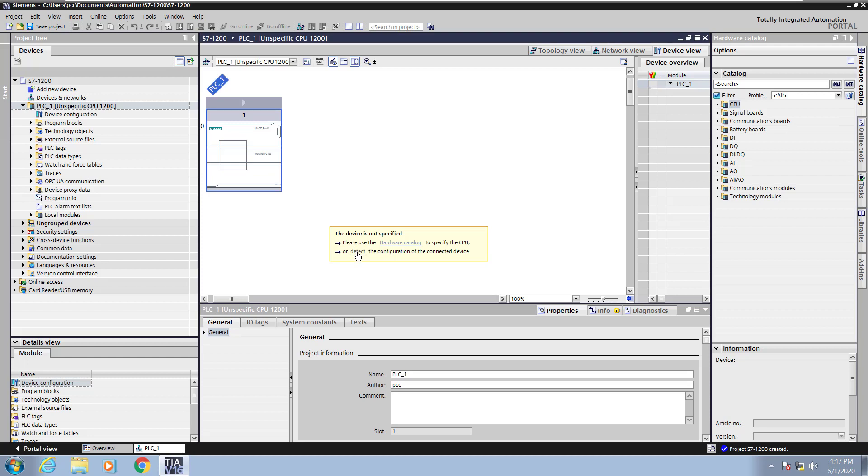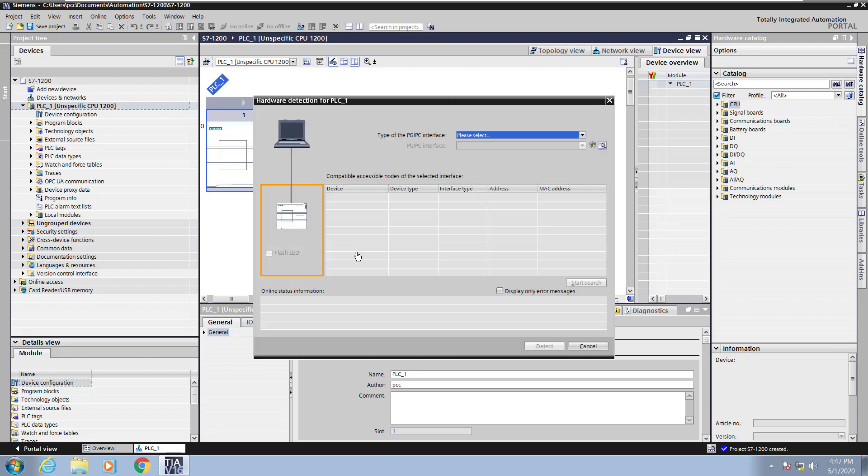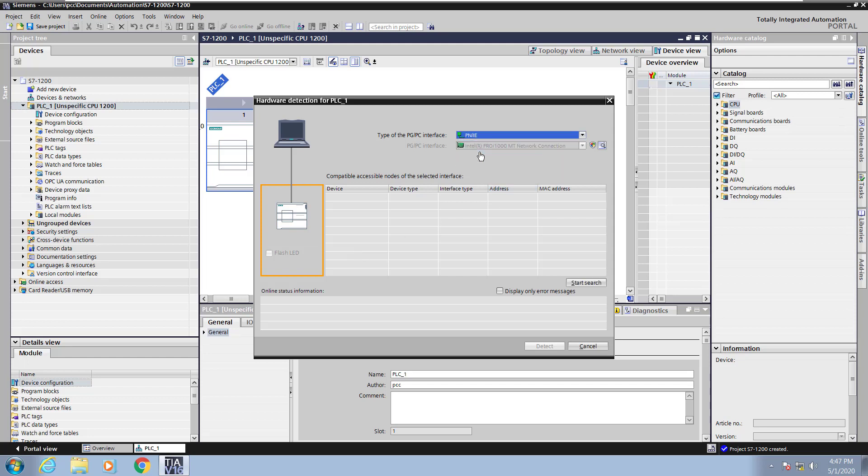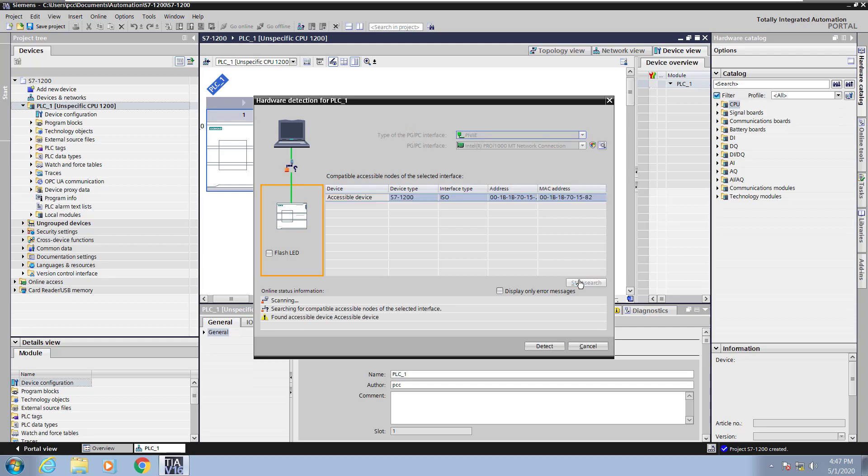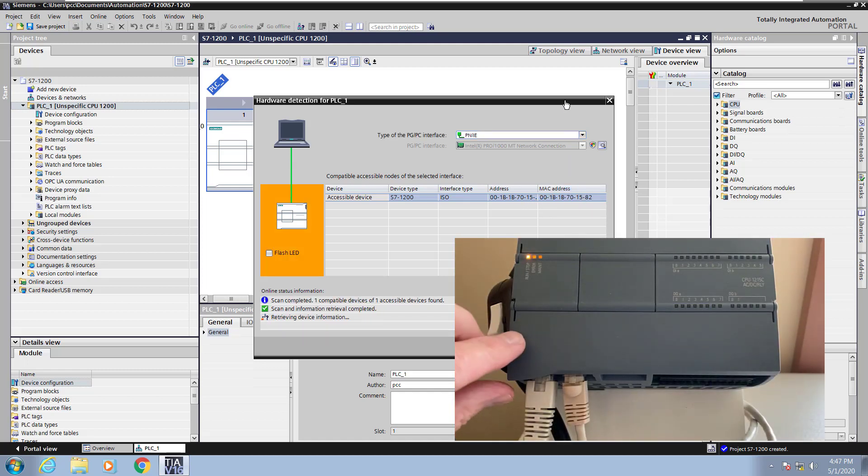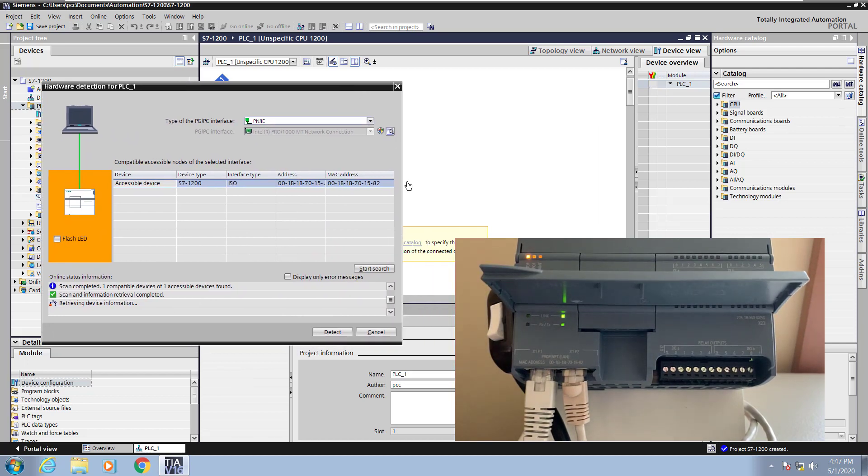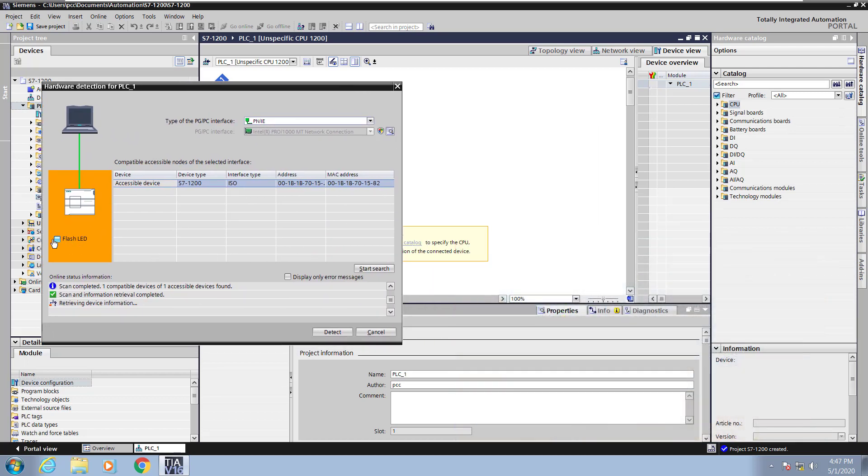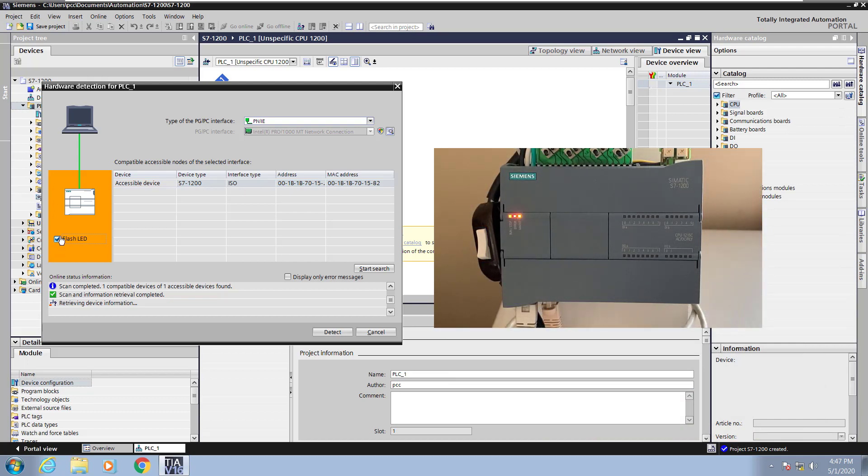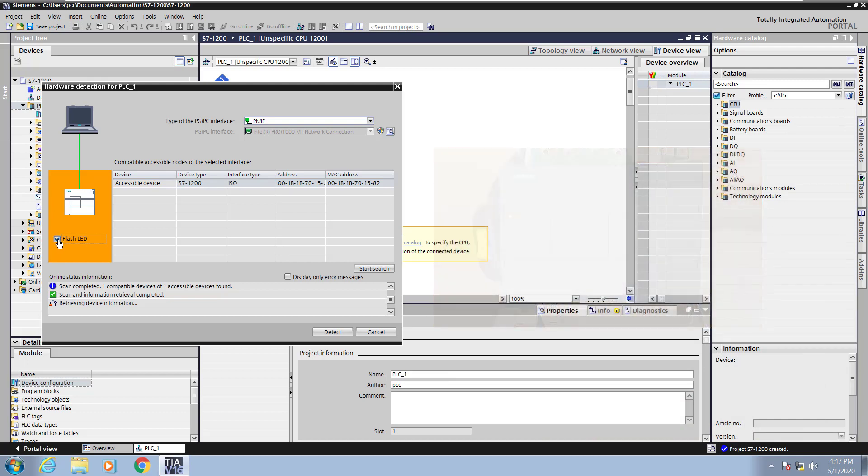When I select the detect feature this is going to bring up a dialog box for hardware detection so I have to select my PROFINET industrial ethernet interface and do a start search. Once a compatible CPU is found it will show up in the list. Right now the PLC does not have an IP address found so we can only see the MAC address of it. The MAC address can be found by lifting up the cover on the CPU and then locating it right above the ethernet ports. You can also flash the LEDs of the CPU to identify a particular CPU to make sure that you are detecting the proper CPU.